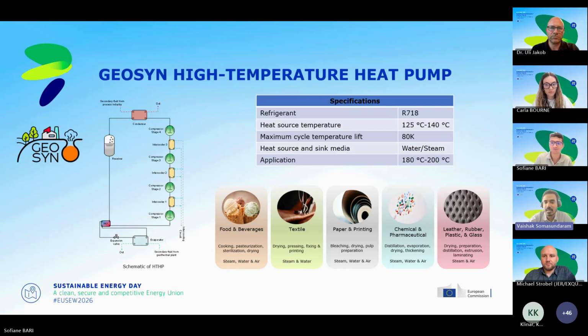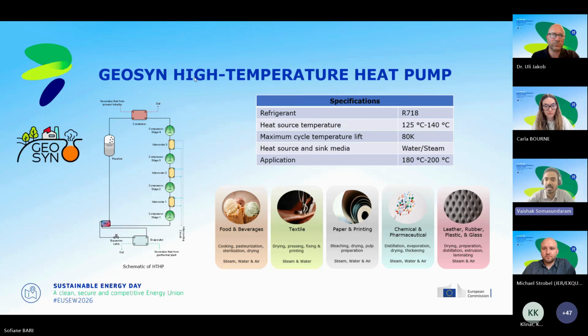For this application we are using water as the refrigerant, because for applications where the sink temperature is above roughly 160 degrees centigrade, water is the best refrigerant for that range, and its performance increases with the rise in condensing temperature.